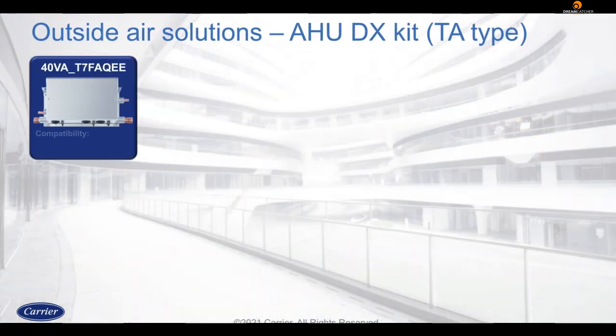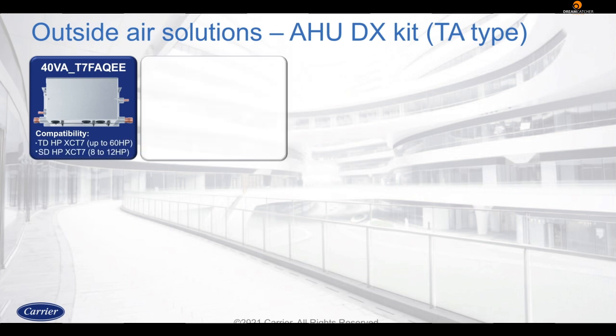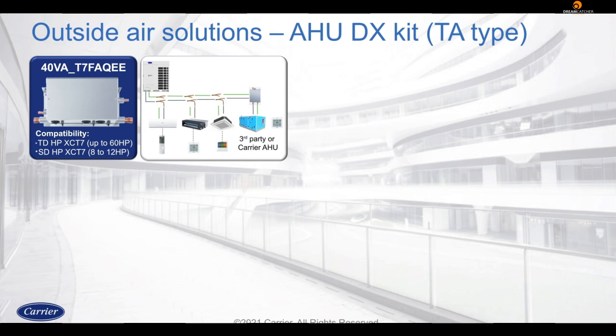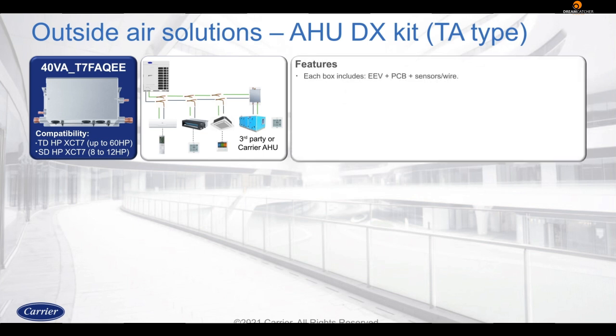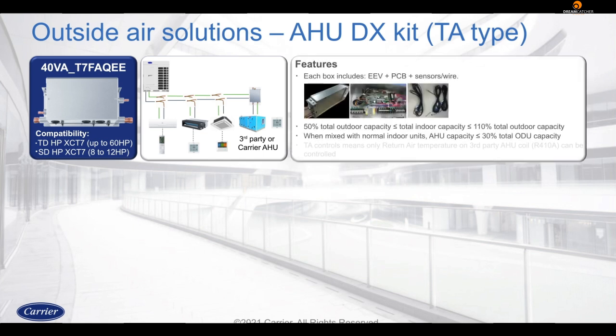The direct expansion kit for AHU has 2 types, TA and DDC type. TA type has 2 models from which you can choose depending on the capacity. Each box contains an expansion valve, PCB, sensors, and wires. You will need the controller but have to order it separately as it is an optional item. Here are some of its features. TA-type control based on return air temperature on AHU coil.